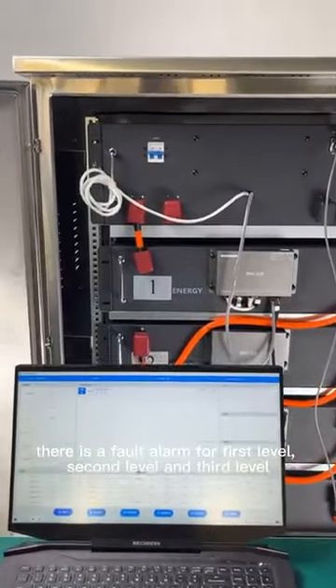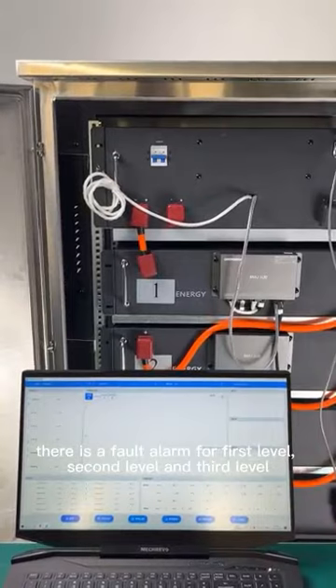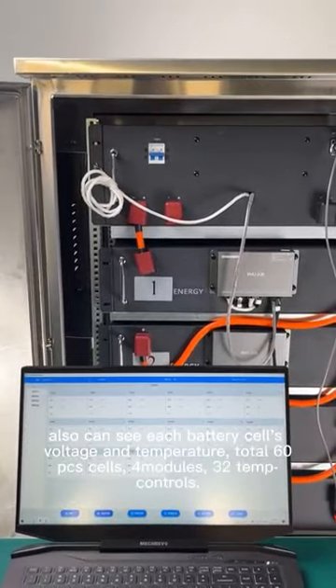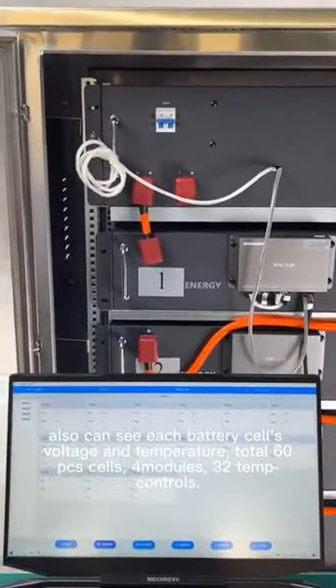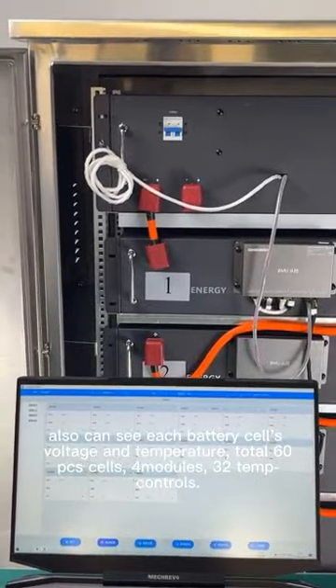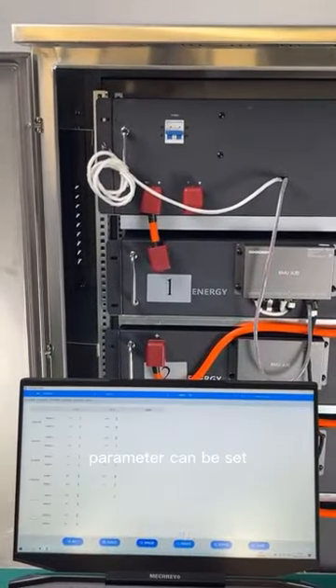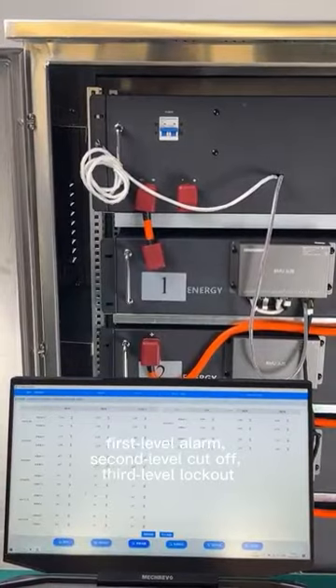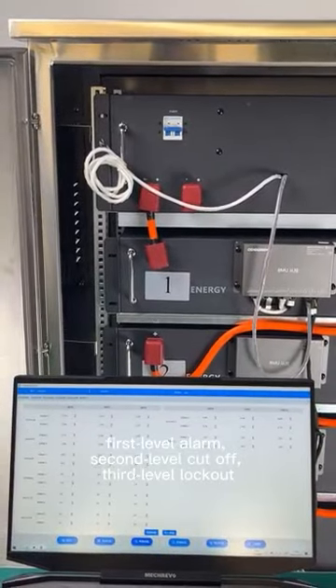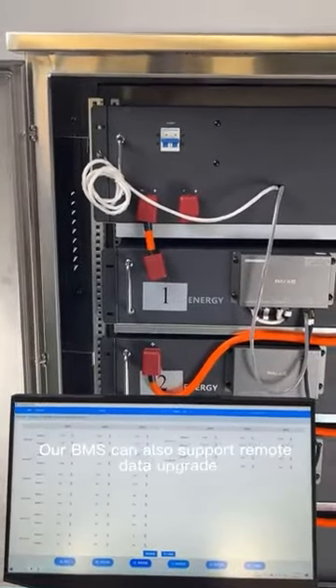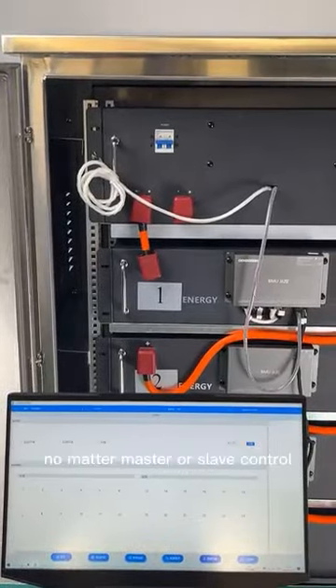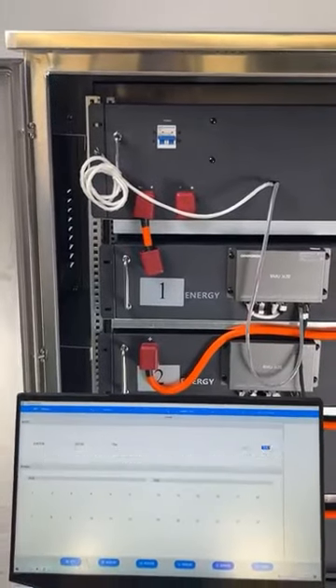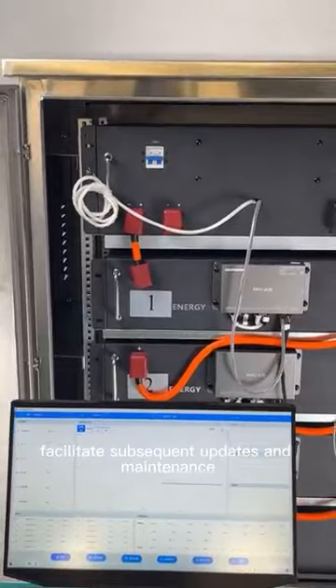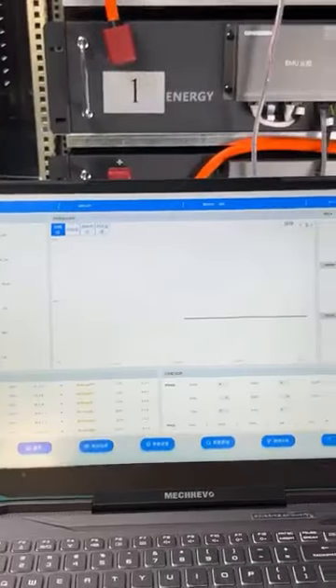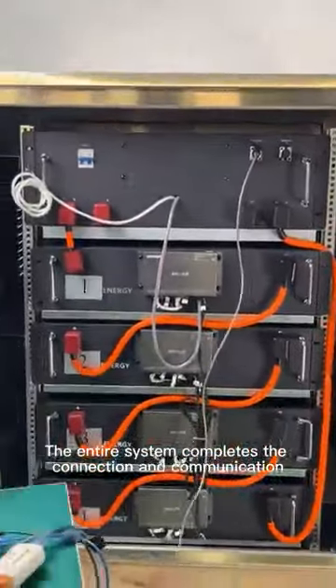There is a fault alarm for first level, second level and third level. Also can see each battery cell's voltage and temperature. Total 60 pieces cells, 4 modules, 32 temp controls. Parameter can be set. First level alarm, second level cutoff, third level lockout. Our BMS can also support remote data upgrade, no matter master or slave control. Facilitate subsequent updates and maintenance. The entire system completes the connection and communication.